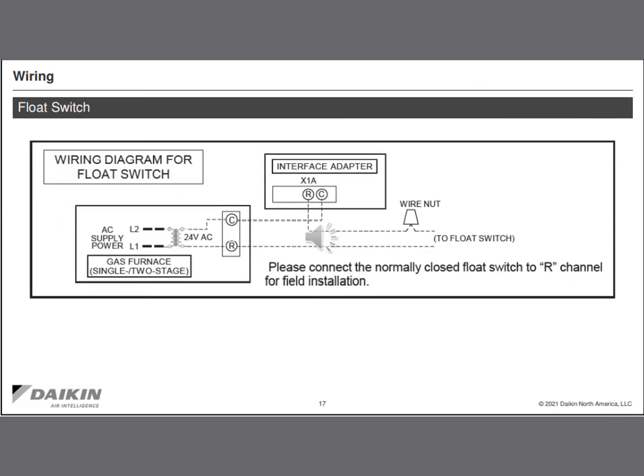If we have a float switch or an emergency switch of some sort where we want to shut this equipment down, perhaps on a load cycling device or some sort of a condensate protection, we have that ability to wire that into the interface adapter on X1A.